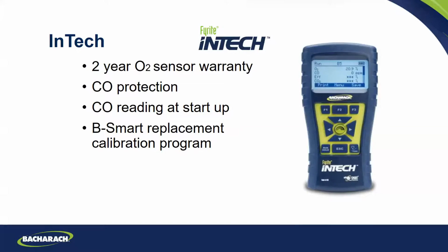So the protocol is to go outside and turn it on if you think CO is in that building. You turn it on outside, you zero the outside atmosphere. That's a great protocol. However, if you're doing work in some cities, the ambient air could be 12 to 15 ppm outside. Or it could be 10 degrees outside, and I don't think anyone's going to walk outside.